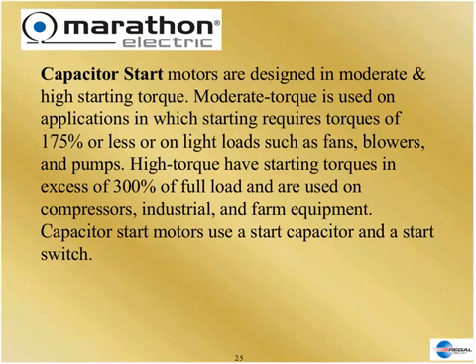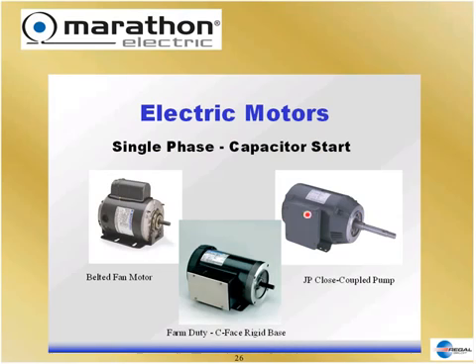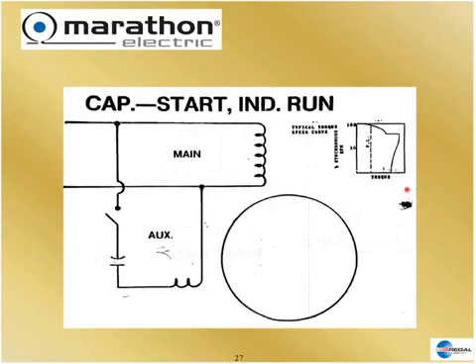What if we have a constant torque load and need a lot of starting torque that a split-phase motor can't provide? There's another single-phase motor that's more of a general-purpose motor: the capacitor start motor. Capacitor start motors utilize a capacitor to give the motor more torque at starting. The capacitor is located in a side box or a small housing called a doghouse or capacitor cover. Here's a speed-torque curve — notice the large amount of torque available to start and accelerate the motor.